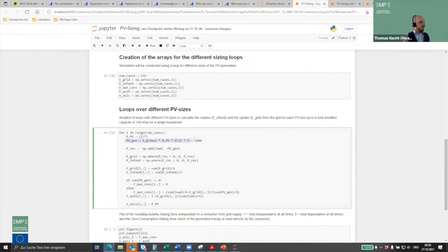This is the part where technical modelers can go nuts, because calculating the PV power from the global irradiation can be as simple as this formula, but you could also have a multitude of different parameters in there: the outside temperature, which affects the efficiency of the PV modules, the temperature of the inverter, dust on the panels, aging of the panels, angle of the sun, angle of the PV generator, and so on and so forth.